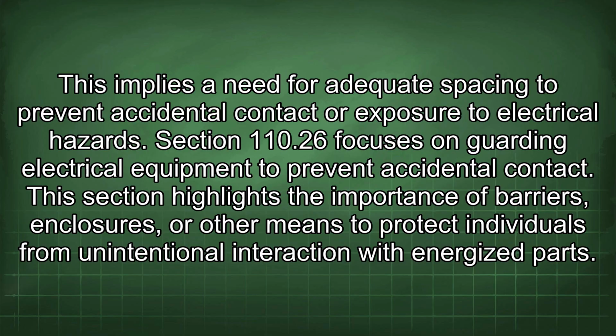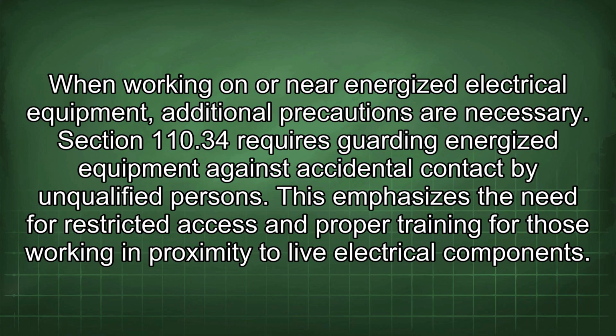Section 110.26 focuses on guarding electrical equipment to prevent accidental contact. This section highlights the importance of barriers, enclosures, or other means to protect individuals from unintentional interaction with energized parts. When working on or near energized electrical equipment, additional precautions are necessary. Section 110.34 requires guarding energized equipment against accidental contact by unqualified persons. This emphasizes the need for restricted access and proper training for those working in proximity to live electrical components.